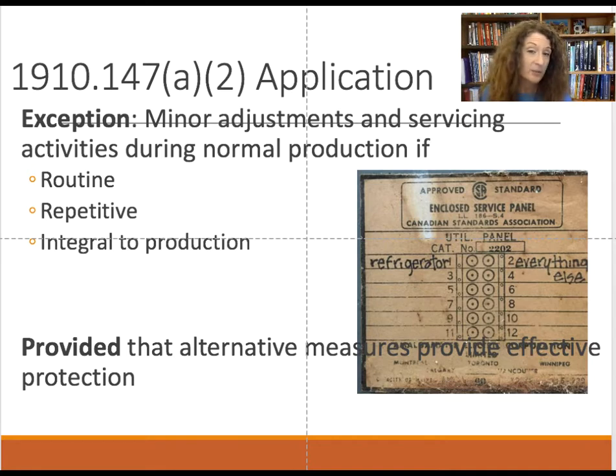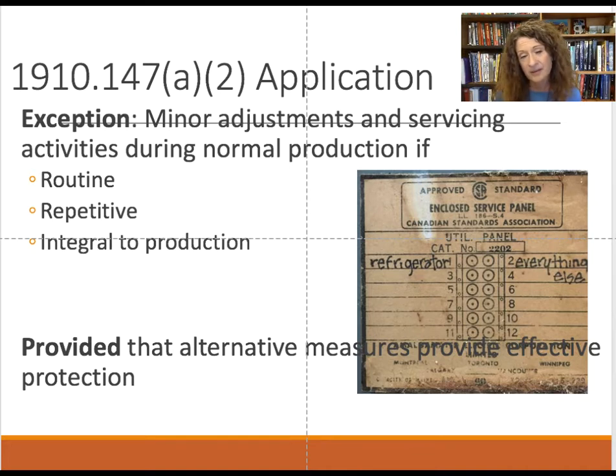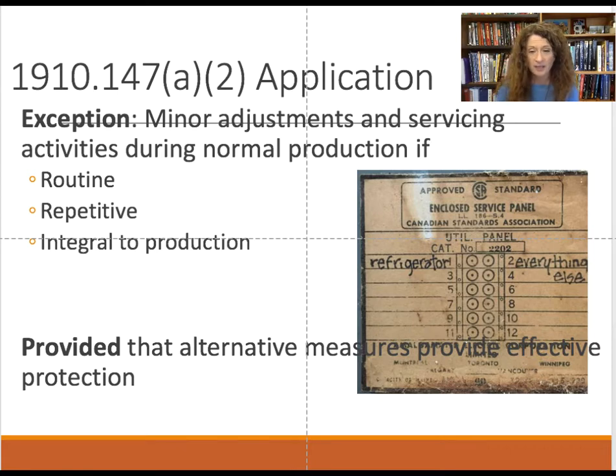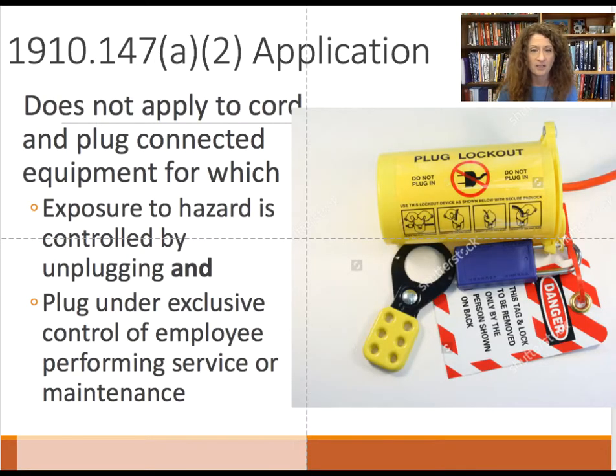Here is an example of a panel that is poorly labeled — people wouldn't know what to lock out or tag out. That's part of electrical safety but also applies to lockout-tagout because people need to know what turns a machine off and how to lock it out and tag it out appropriately.